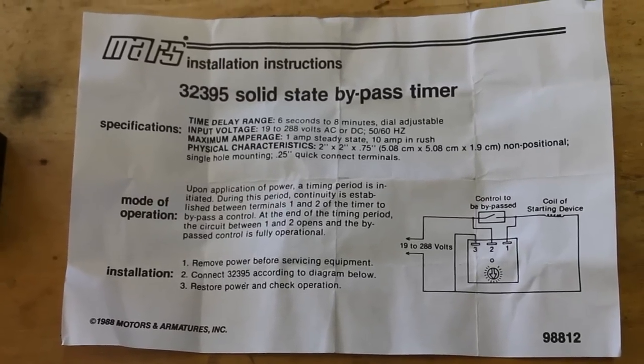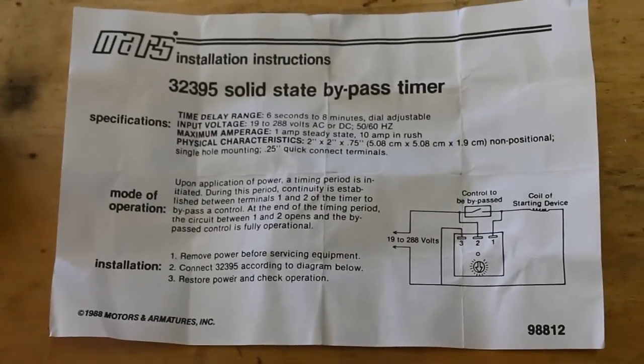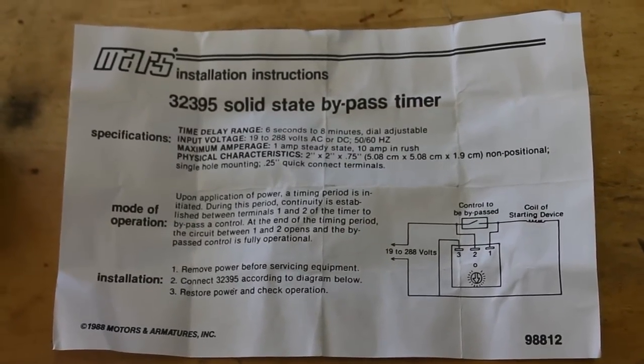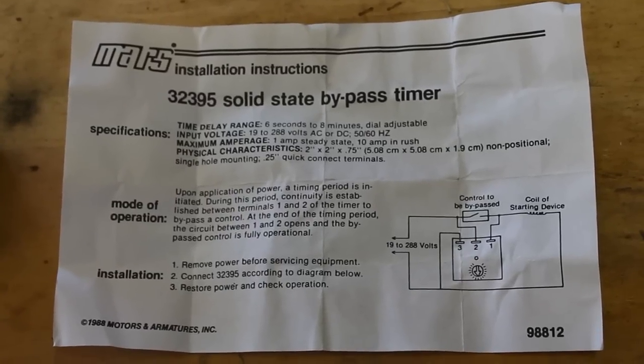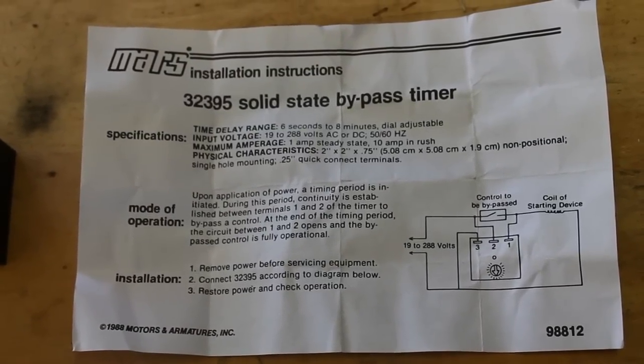I would use this to bypass a low-pressure controller to ensure smooth unit startup. If it's extremely cold outside, you'd be in danger of tripping the low-pressure switch during startup.